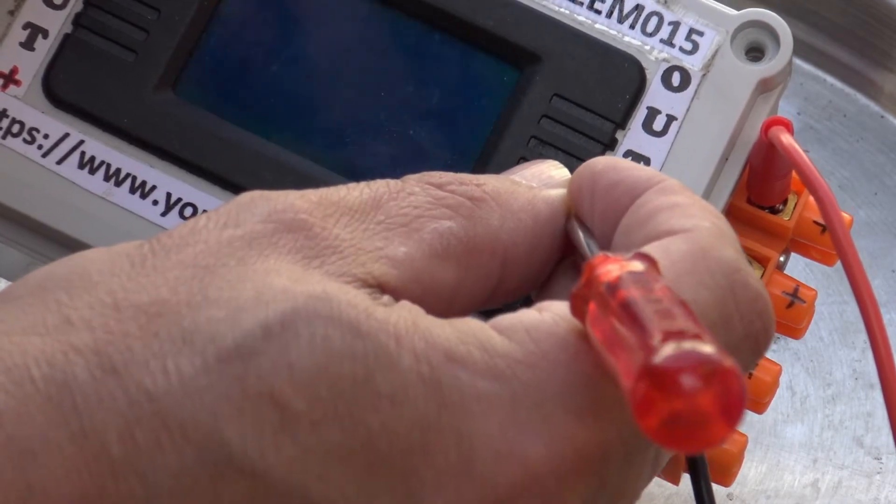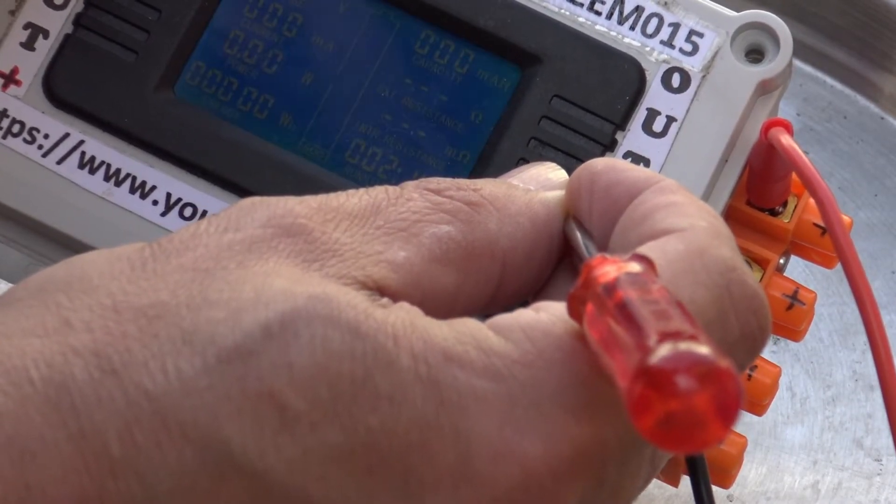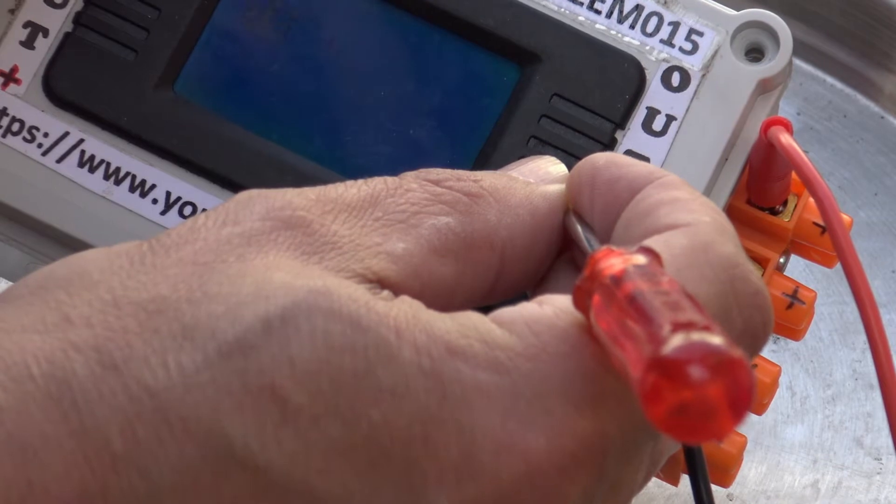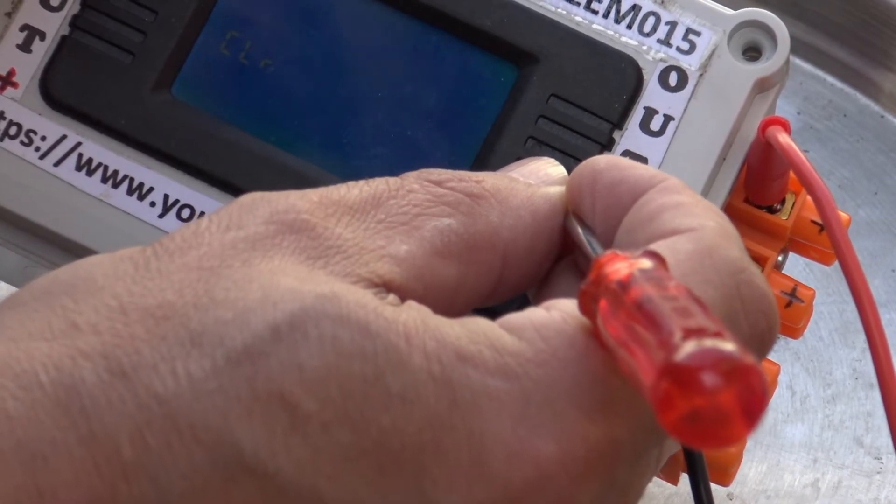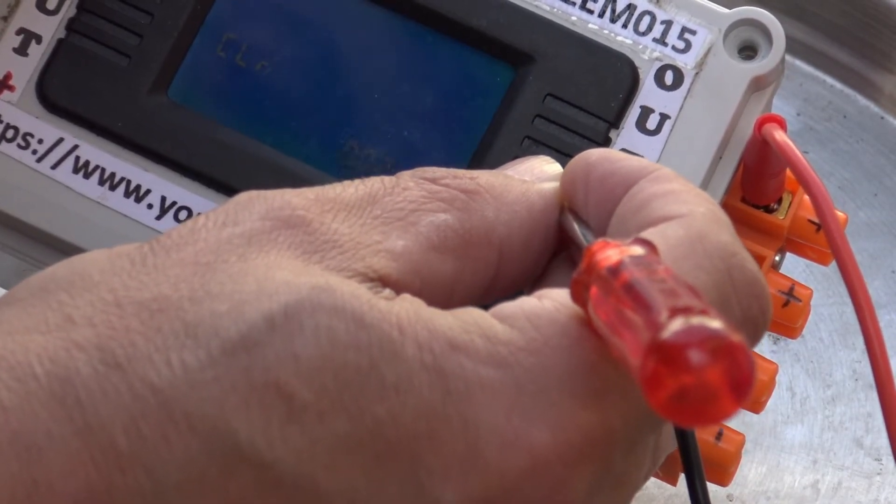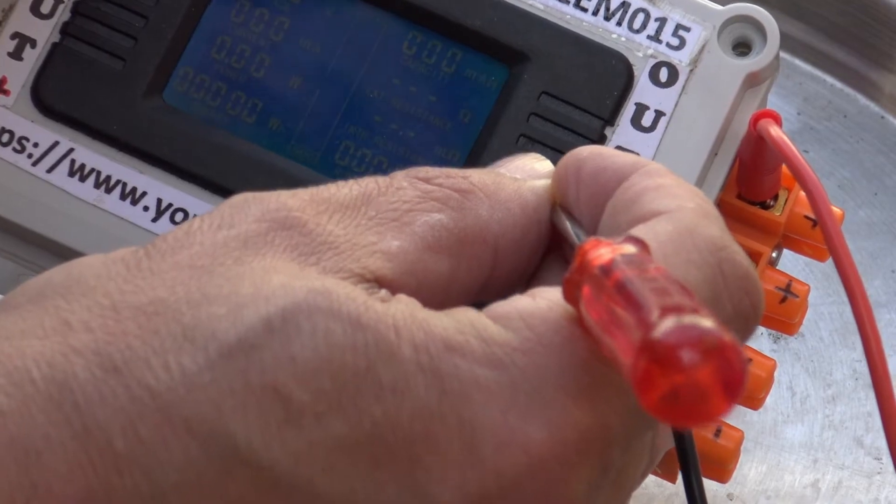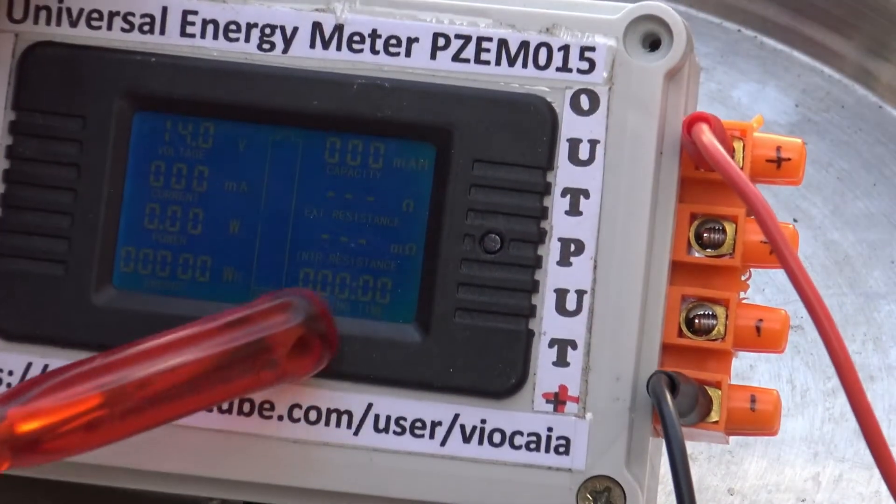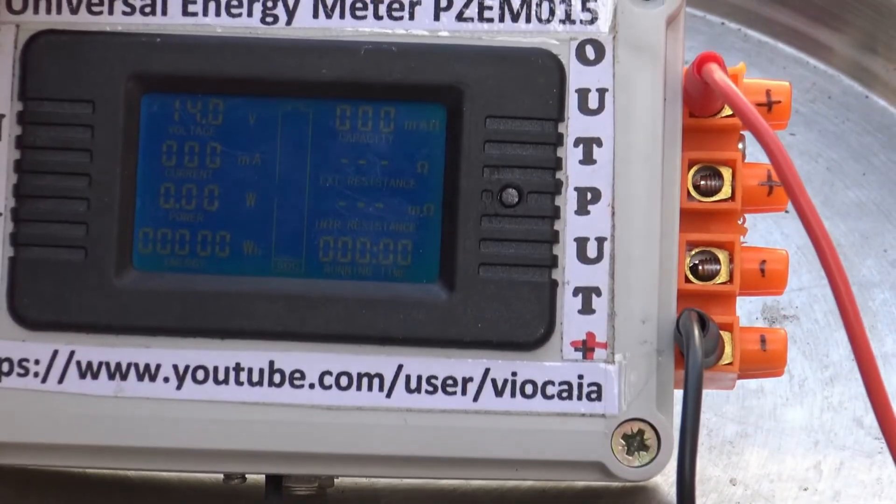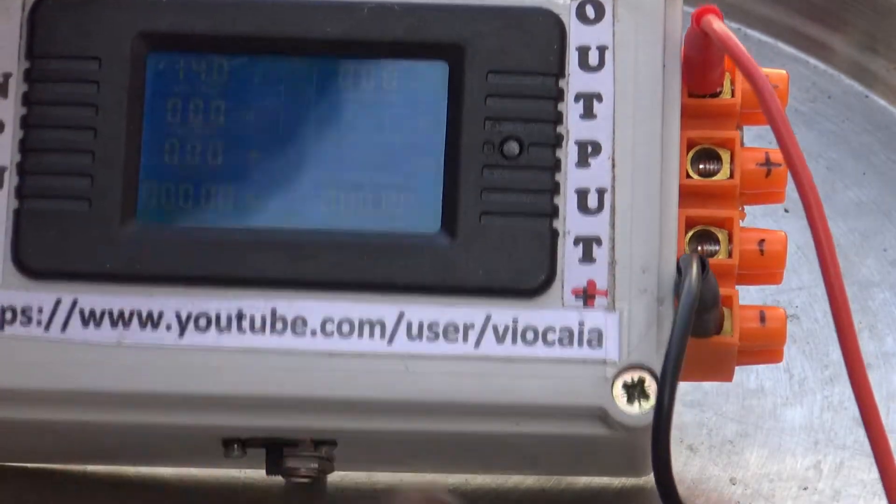And then reset also the amperage, the current meter or counter, in fact. Okay, and the last one, the timer, to zero. What's nice about the PZEM-015 is that the timer is only running when it feels the current. You see the timer down here, it's only running when it feels the current in the circuit.